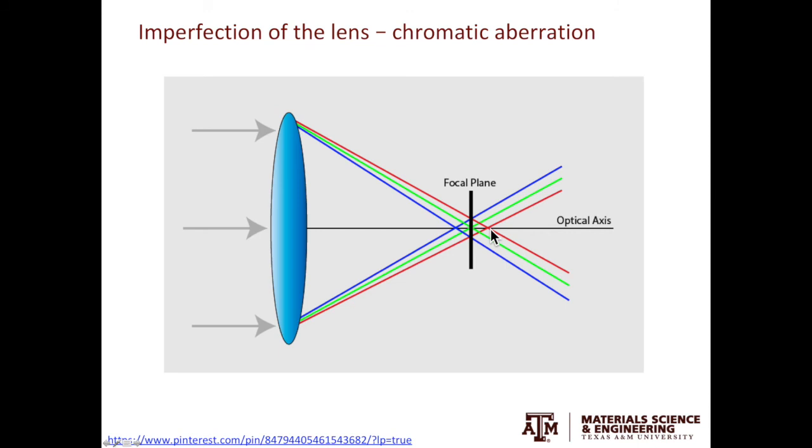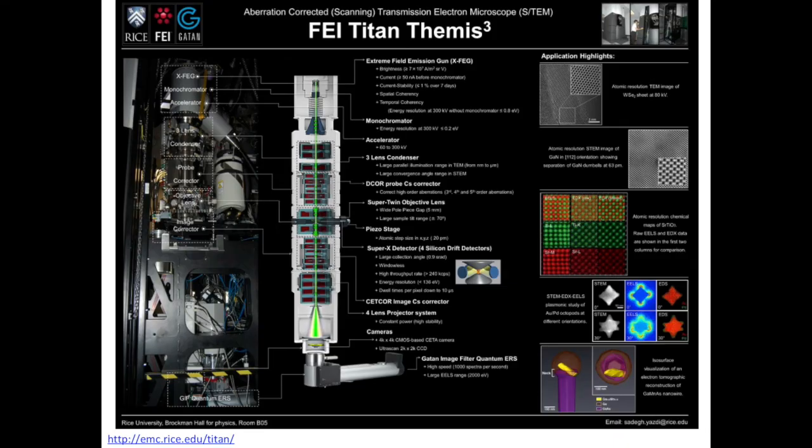To correct the spherical aberration and chromatic aberration in TEM is very expensive. I took this poster from Rice University. Rice has a FEI Titan Themis³ TEM. The TEM is equipped with a monochromator and two aberration correctors. The monochromator sits in the electron source to reduce the energy spread of the electron beam.